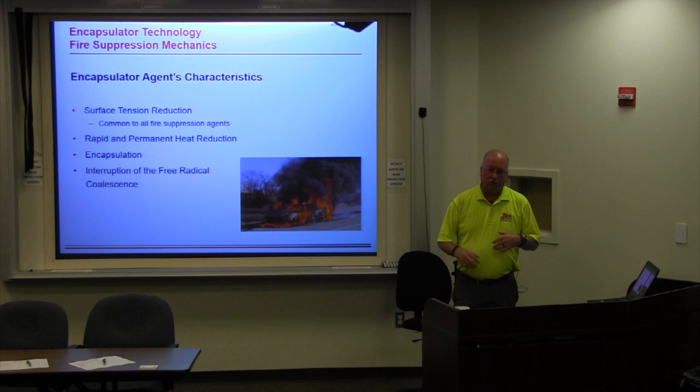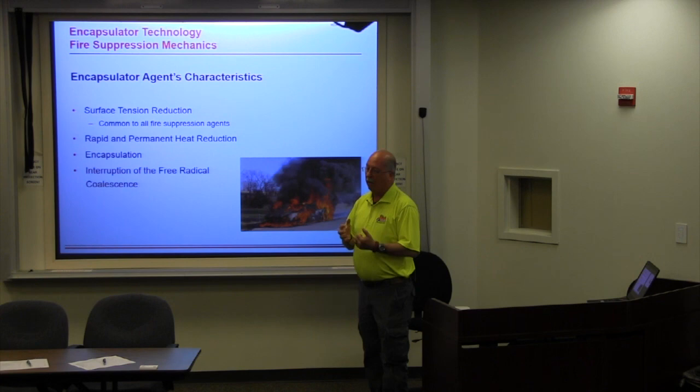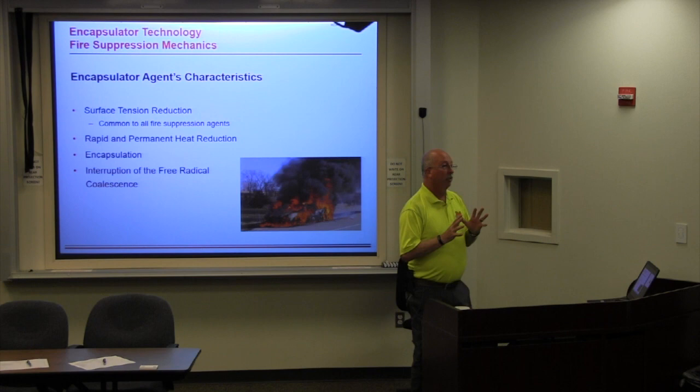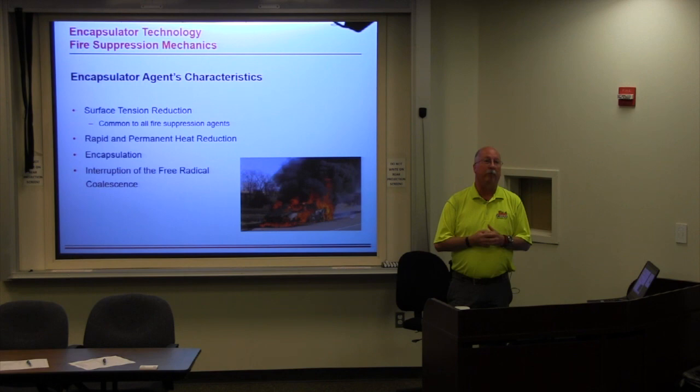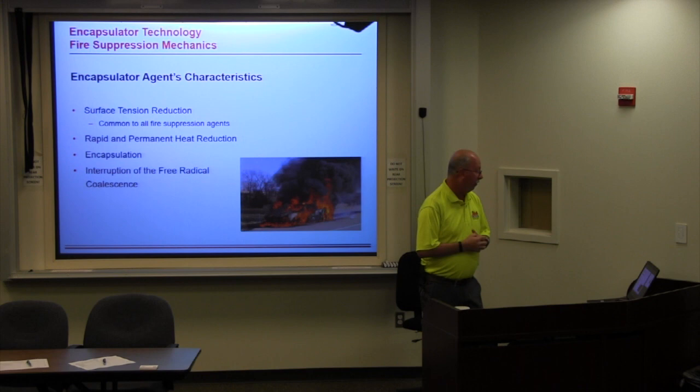So we talked about surface tension reduction. That's common with all of them. But where we start becoming a little bit different is the rapid and permanent heat reduction. I take temperatures in excess of 1500 degrees and I can drop them down to around 100 degrees in a matter of seconds. And it's permanent. Once I've taken the heat out, it's not going to come back. It's not going to sneak back up on you. It's gone. The other thing is the encapsulation. We'll talk about all three of these things. And lastly, the interruption of the free radical coalescence.